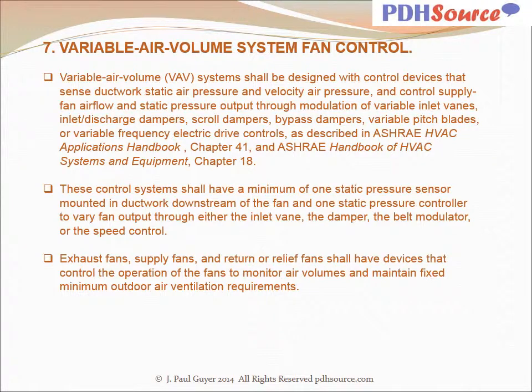Variable air volume VAV systems shall be designed with control devices that sense ductwork static air pressure and velocity air pressure and control supply fan airflow and static pressure output through modulation of variable inlet vanes, inlet discharge dampers, scroll dampers, bypass dampers, variable pitch blades, or variable frequency electric drive controllers as described in ASHRAE Handbook, Applications Handbook, Chapter 41, and ASHRAE Systems and Equipment Handbook, Chapter 18.